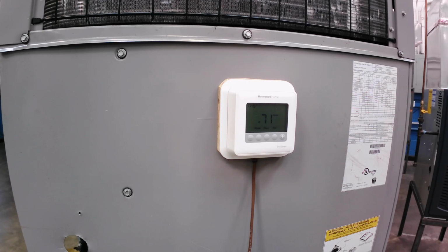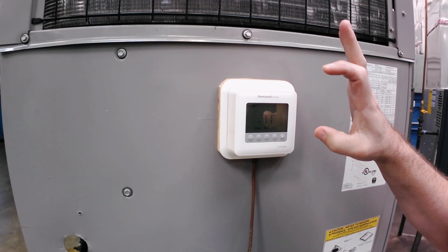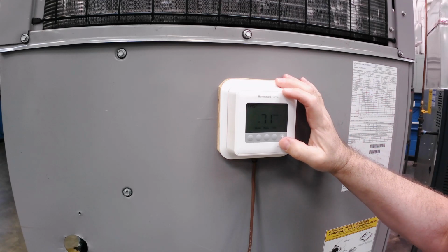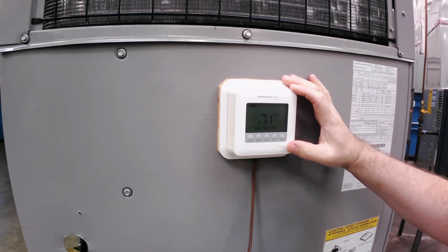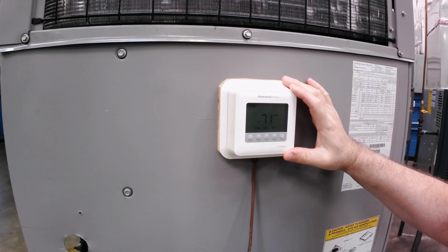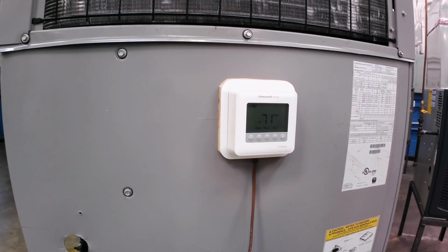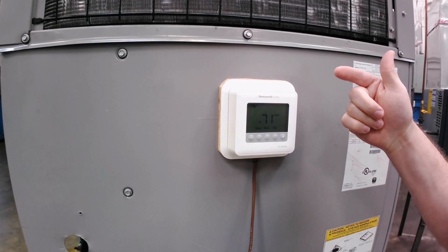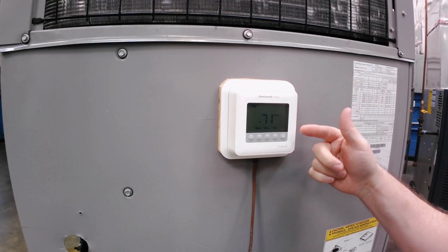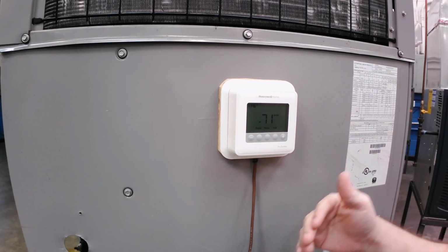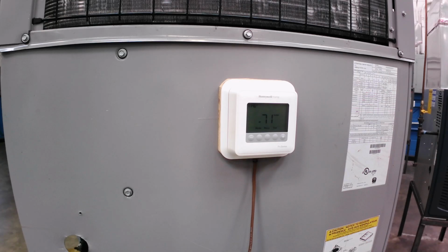So the thermostat's the brain of the operation. For me personally, I think about our low voltage and high voltage working together with the thermostat. The thermostat tells it what to do - tells the system when to work and who to work. So the sequence of operation I keep in mind is the thermostat calls for something, and all those wires we wire on the sub base go to a coil - a relay coil for the indoor fan, a contactor coil for the outside unit, a solenoid coil for the reversing valve, or whatever for heat strips. The list goes on and on depending on what you have. So the thermostat controls the coil, the coil moves a switch in that relay or contactor, and that switch passes high voltage power into a motor or a heat strip or something like that.